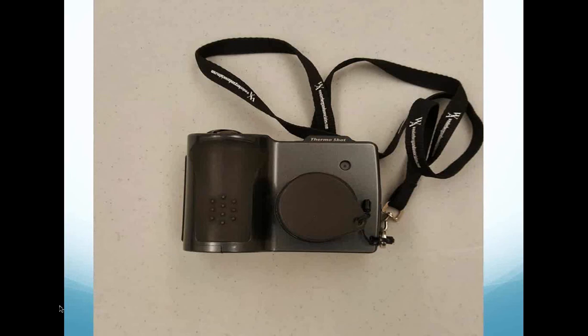This is a picture of just a simple thermal imaging camera, so I can look at the thermal image and the stratification of the vapor and the condensate in a steam application. But I love to listen to it. I love to shoot it with temperature, and I like to actually know, am I on? Has the steam strainer been blown down? Has the steam equipment been touched recently? When was the last cycle of maintenance in the facility?